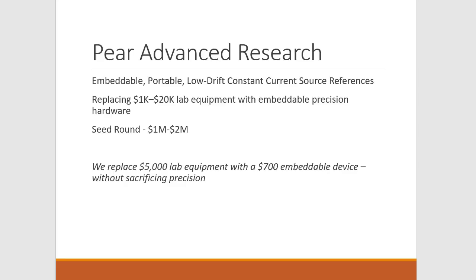We are working on a precision constant current source with very low drift, ideally 0% current drift. We've designed a 0.25 milliamp current source that's small, embeddable, and has low current drift, for customers in test engineering who do calibration setups and want a current source embeddable in a test system engineered product, or used as a standalone.